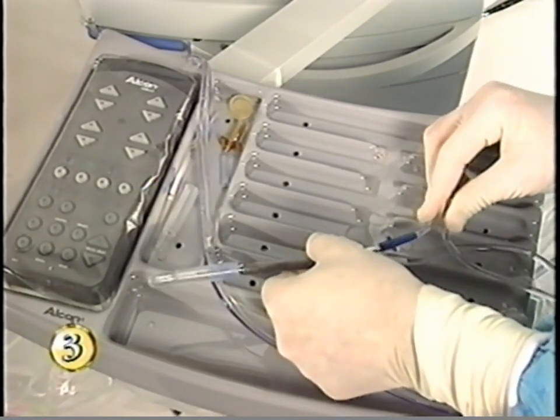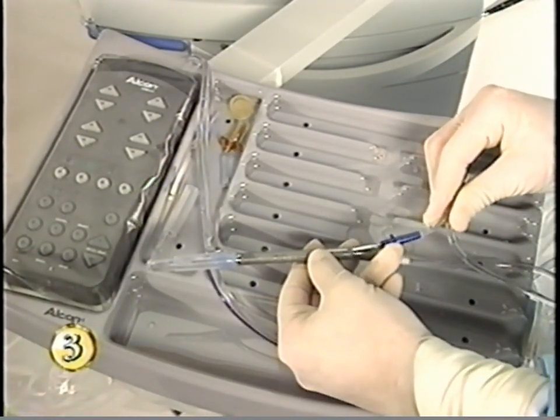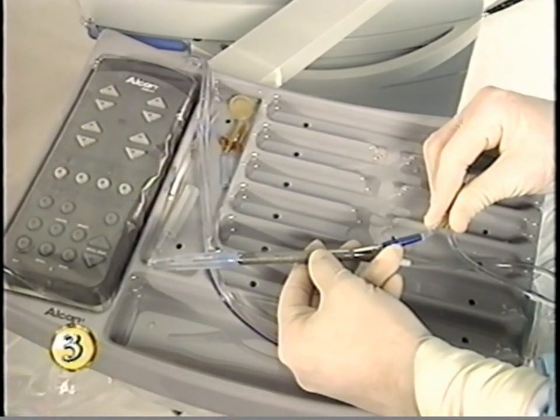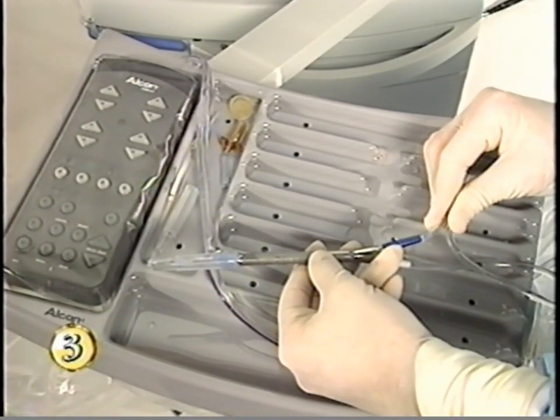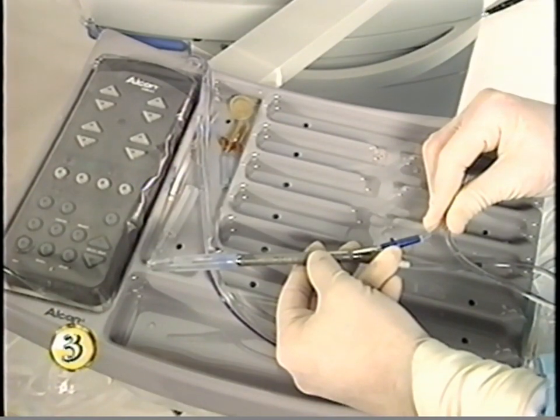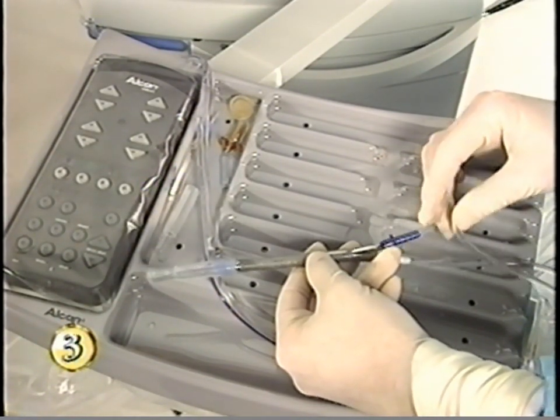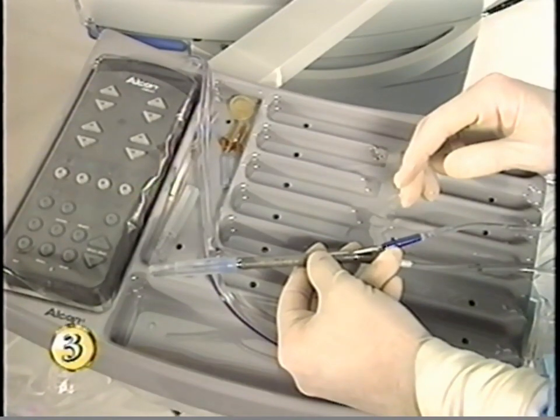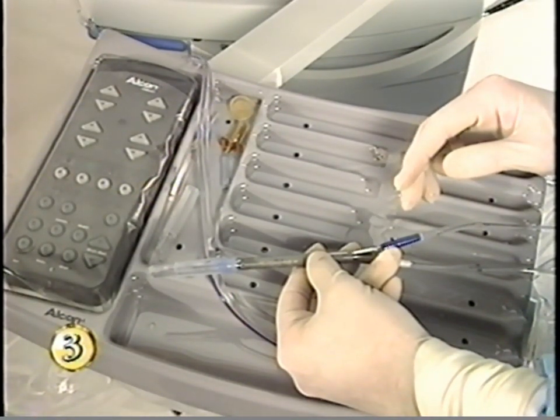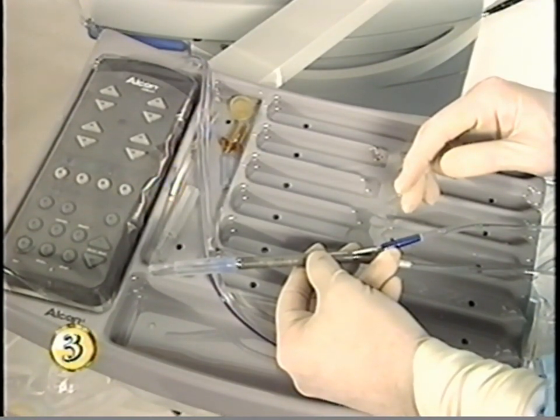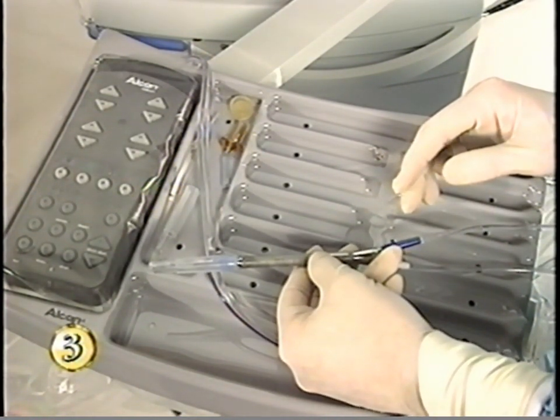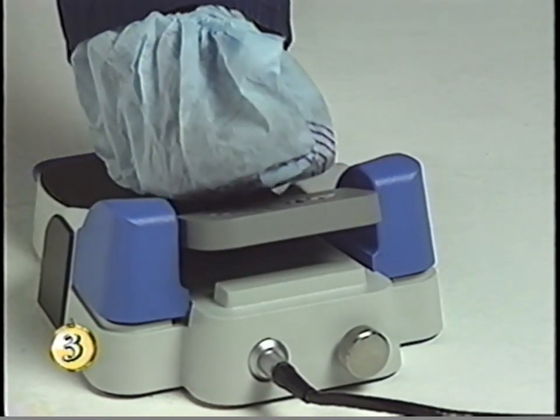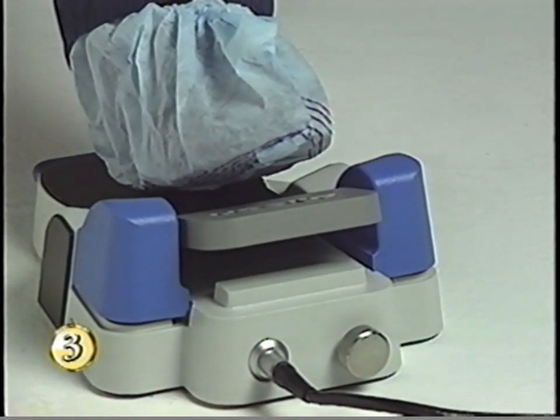Pinch off the blue aspiration line near the handpiece to simulate an occlusion. Press and hold the foot switch in position 2 to start fluid flow. Continue to pinch for 5 seconds, after which the pump should stop. Release the pinch to open the aspiration tubing, noting that the test chamber maintains its shape or dimples slightly. If not, the fluidics test has failed and you should consult the troubleshooting section of the operator's manual. Do not proceed until the problem is solved. Release the foot switch to stop fluid flow.